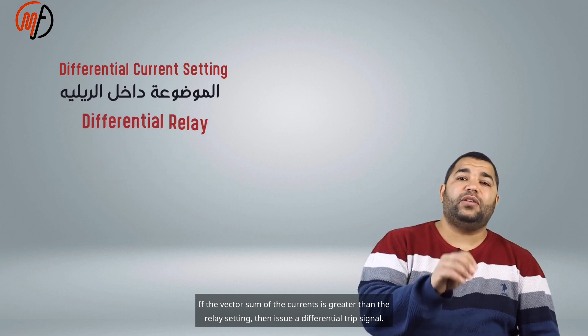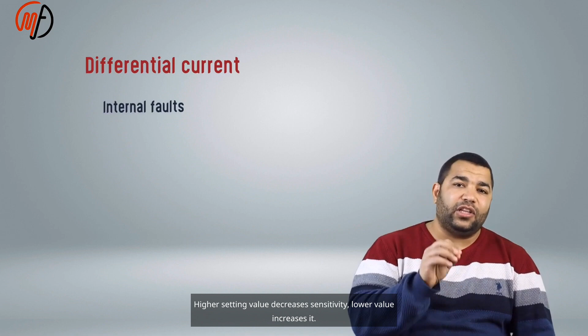If this differential current exceeds the relay setting, it will cause the differential relay to trip. If the vector sum of the currents is greater than the relay setting, then issue a differential trip signal. Thus, differential current indicates internal faults. We set the diff setting to increase safety and avoid false trips due to CT errors. Higher setting value decreases sensitivity, lower value increases it.